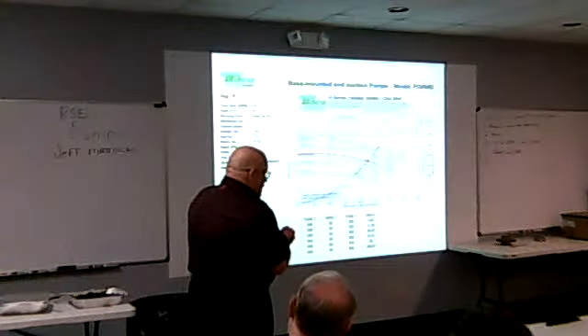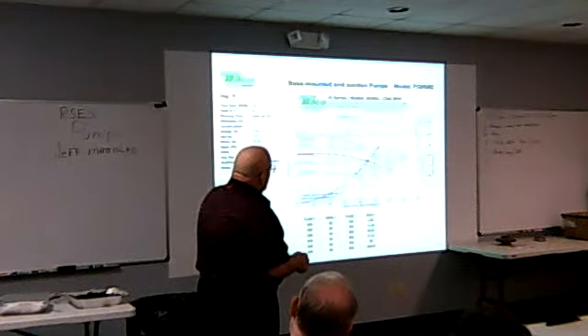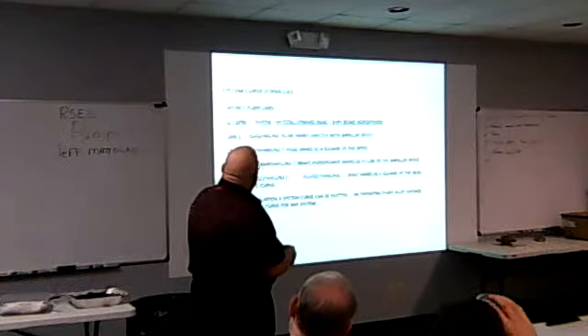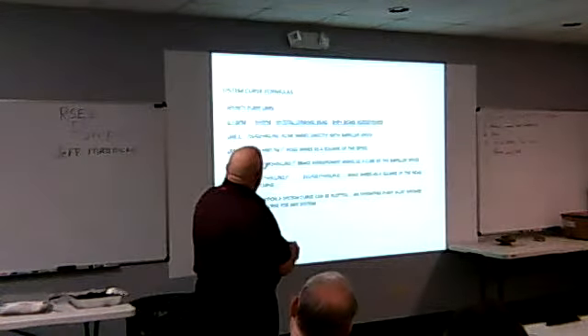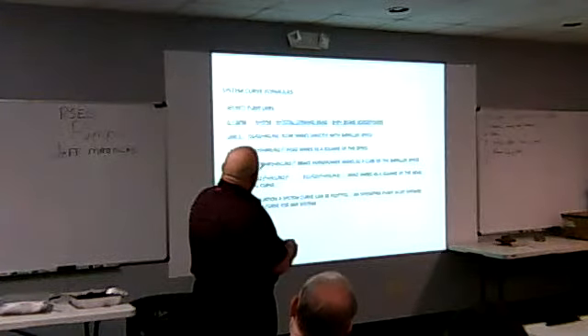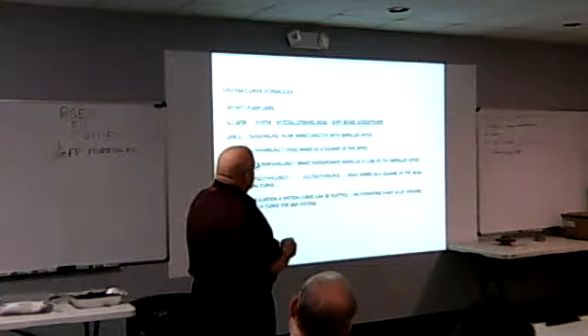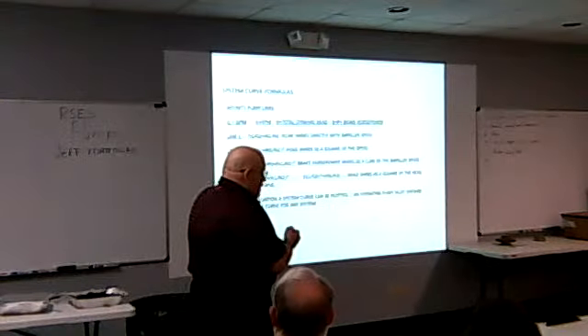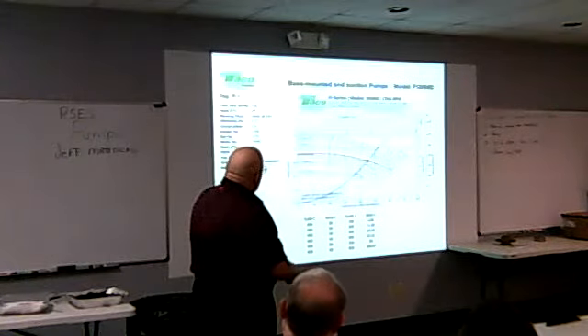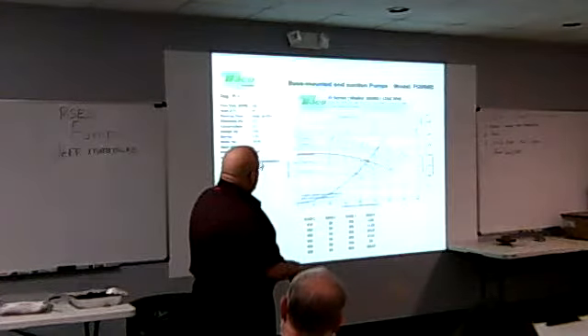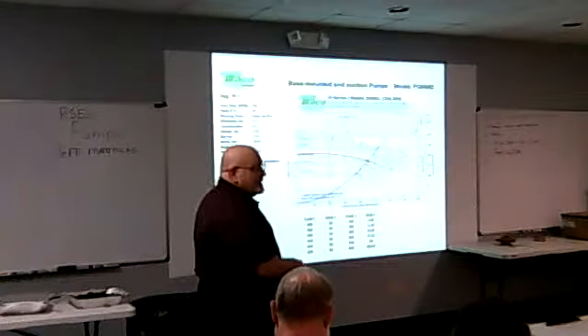For example, here's how you get this system curve. Remember that affinity law we talked about right here? This here, H1 over H2. If I divide by H2, I have H1 over H2 equals N1 over N2 squared, right? Then I can go to the curve. If you really want to make this curve, you can put my first flow in at 450, my head one's at 60, put in my flow 2, I can calculate my second head.